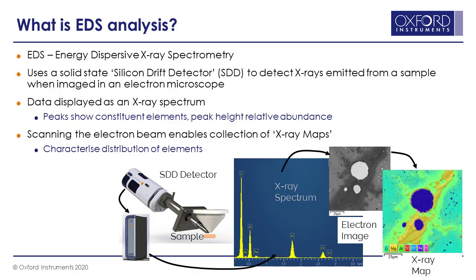What is EDS analysis? EDS stands for energy dispersive X-ray spectroscopy. This is the technique where we use a silicon drift detector to detect the X-rays generated by the interaction between the electron beam and the sample inside the electron microscope. By detecting and processing the X-rays, we can measure and characterize them for every single position on the sample surface. By analyzing the X-ray spectrum, we can say what elements are present — generally the peak height in the spectrum relates to the abundance of the element. By scanning the beam over the sample surface, we create an image and at the same time collect chemical data, reconstructing it into a colorful chemical map showing the variation of chemical elements, allowing us to see and quantify chemistry at any given position.